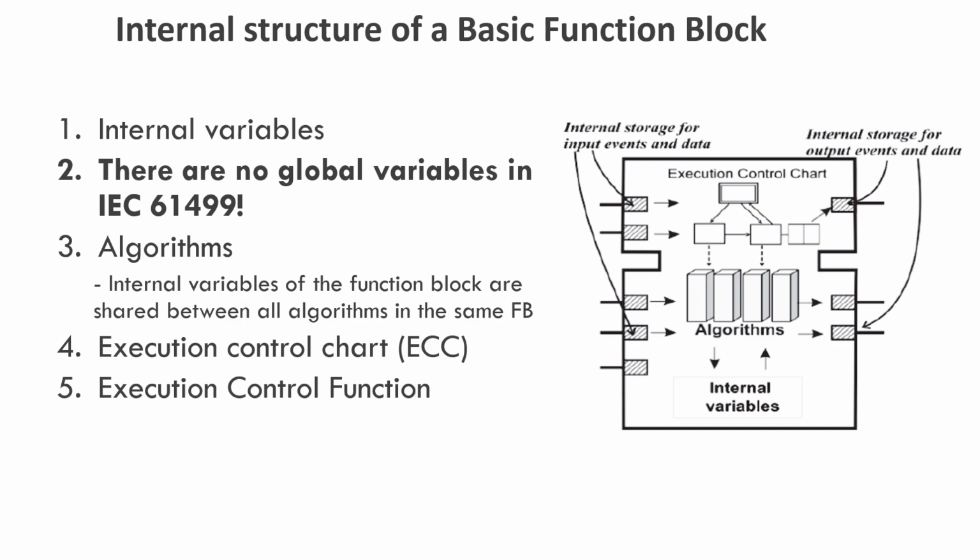You cannot declare variables on the level of application or system configuration. The only place where variables can be declared is in internal variables of basic function block. So you should remember that there are no global variables whatsoever in IEC 61499. And that is done with a purpose.